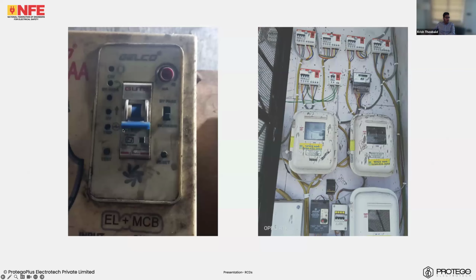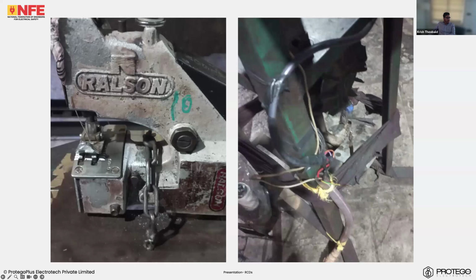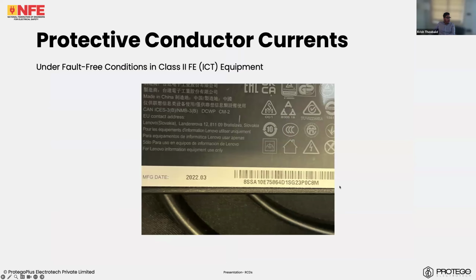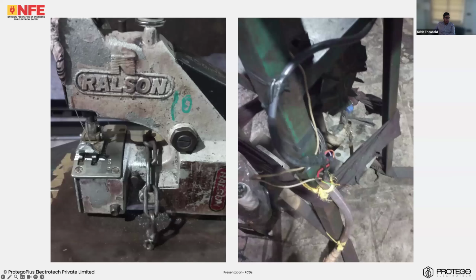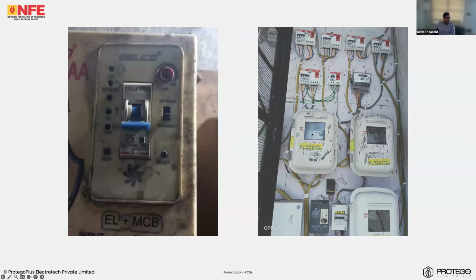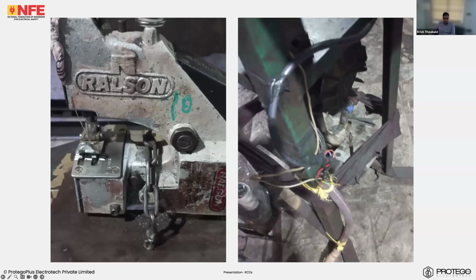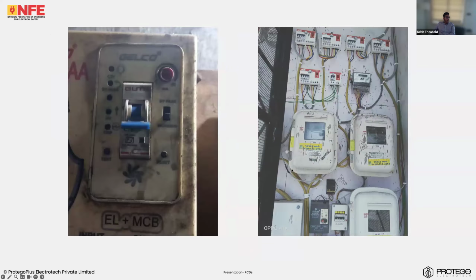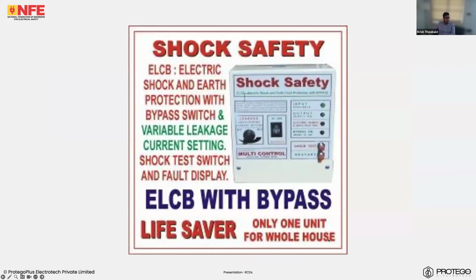We can see here that in several places, this ELCB with bypass has become very common, which is a highly dangerous thing. I don't know how this is ISI marked because this product is not complying to any BIS standard or IEC standard. But you can see many places this is a very common product. This is an example. There was a tailoring workshop where somebody used this ELCB with bypass switch. You can see the protective conductor was interrupted here, and the person actually died. This is a very serious issue. Somebody died because the wrong product was used and the wrong installation practice was used. This is very important. As you will understand, one unit for whole house is complete nonsense.